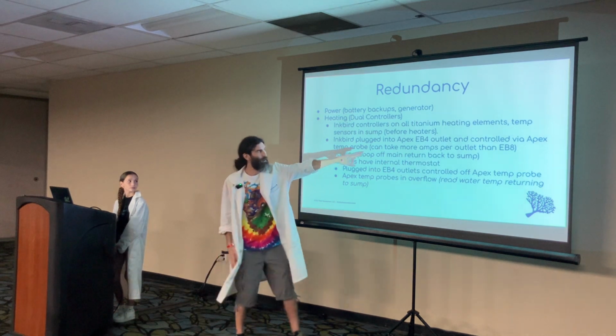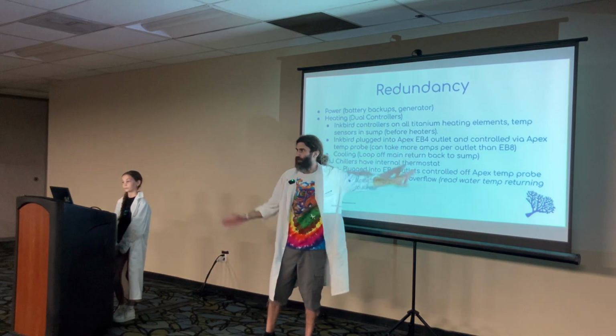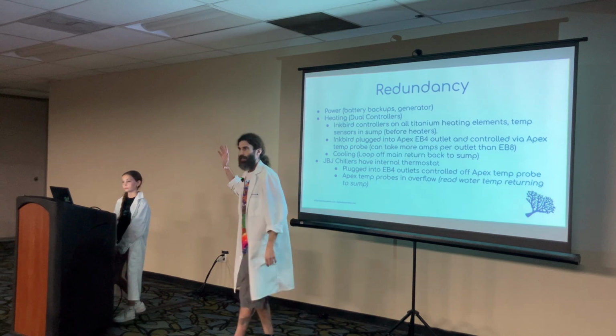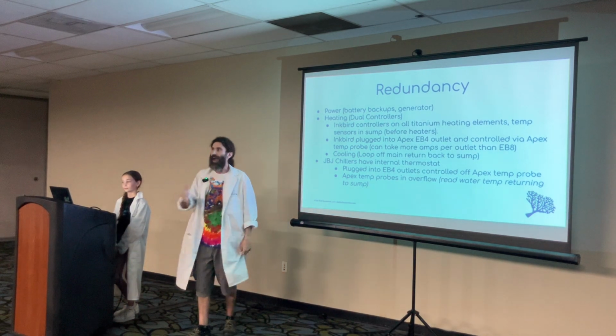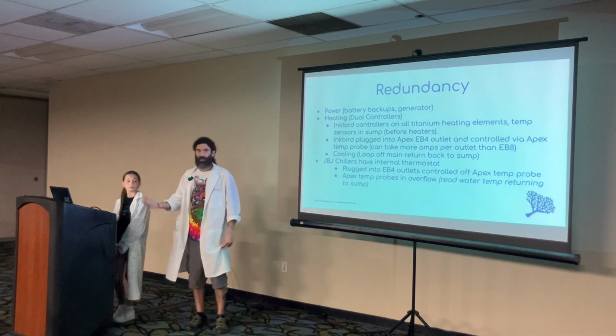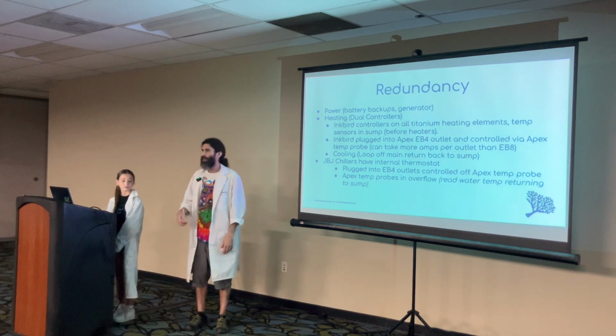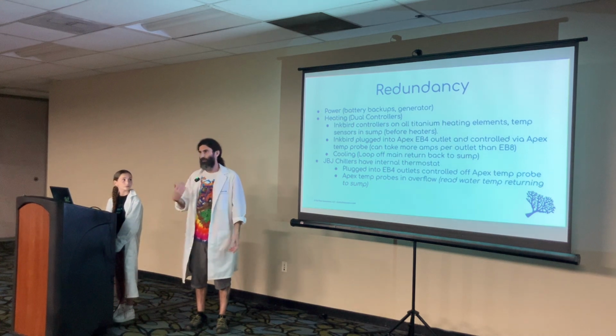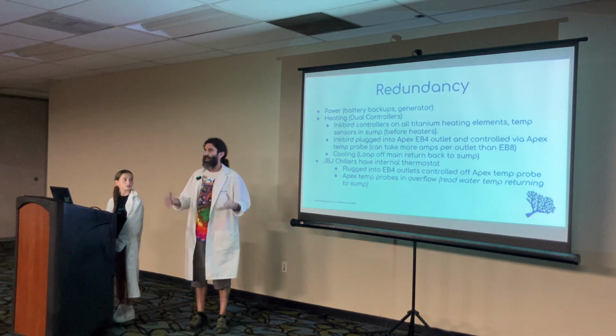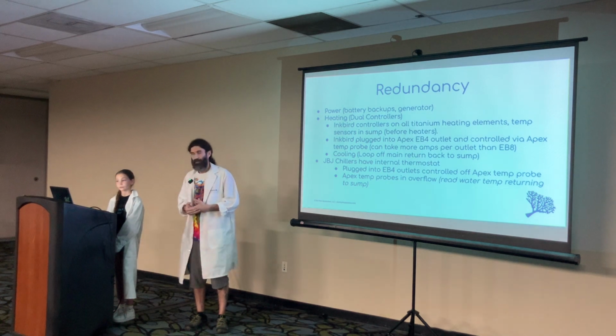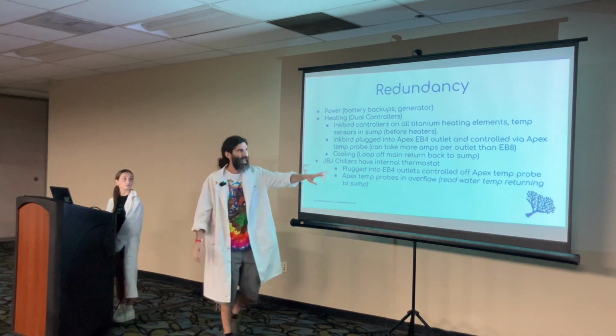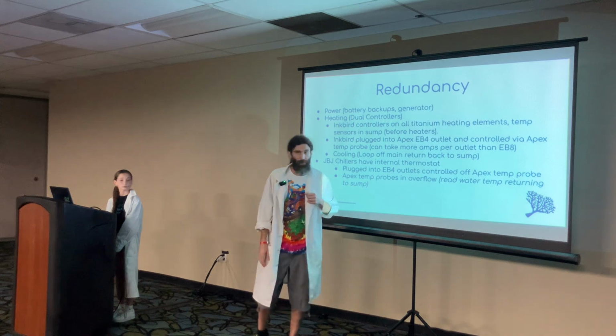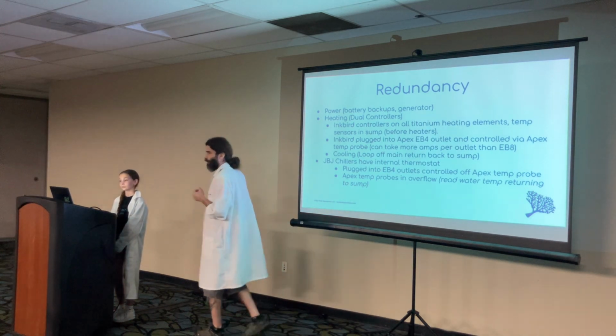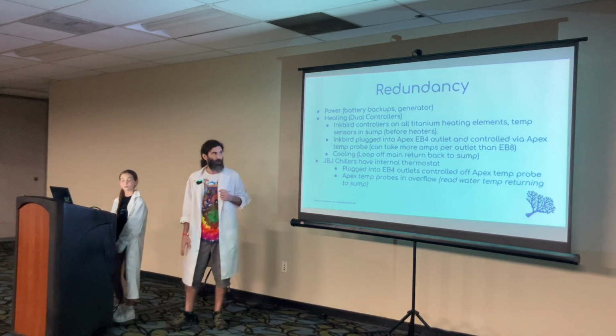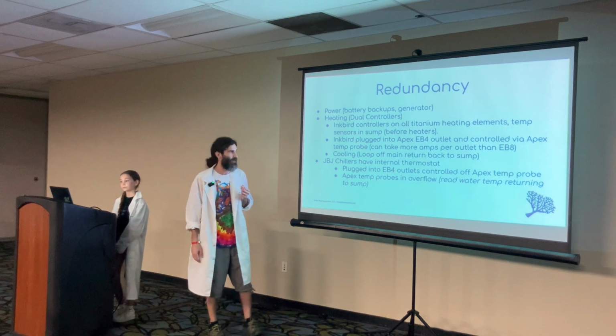We also use the EB4s instead of the EB8s. You guys know they still make EB4s, right? EB4s are awesome, they can take a higher load than the EB8. So if you have, like we have, 600 watt titanium heaters, we can plug those into the 20 amp circuits, and there's 4 plugs, plus I can have my chiller plugged in, and that's going to handle the load on a 20 amp circuit. Versus the EB8s, they don't have as many high capacity outlets on them, so you may burn out an outlet quicker on an EB8. So I use the 4s just because they can handle the extra loads of these higher heaters.